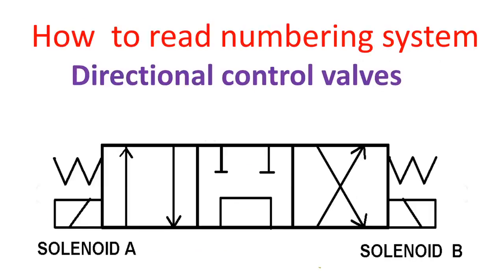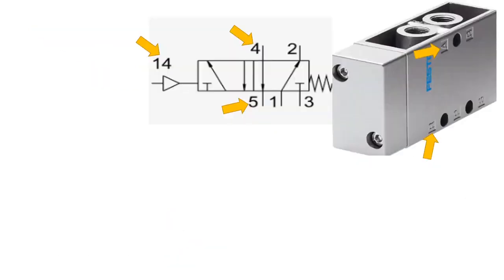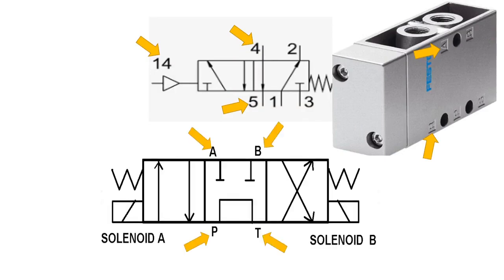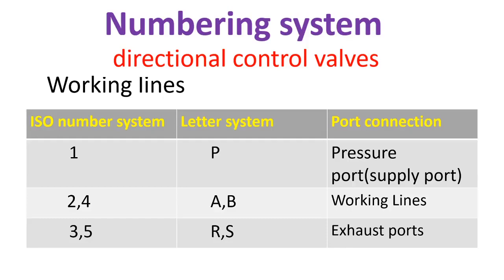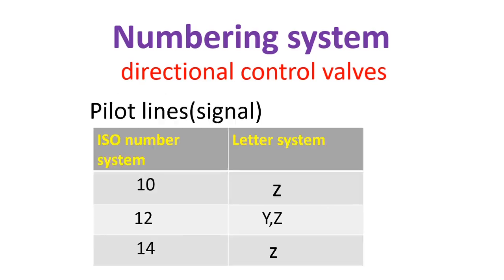Our next topic is how to read the numbering system of directional control valves. If your directional control valve uses numbers or letters for their port designations, here is the equivalent: number one and letter P is the pressure or supply port; numbers two and four, or letters A or B, are working lines; numbers three and five, or letters R and S, are exhaust ports. For pilot lines or signal: 10 is equivalent to Z, 12 is equivalent to Y or Z, and 14 is equivalent to Z.